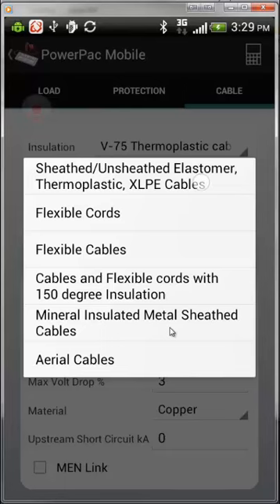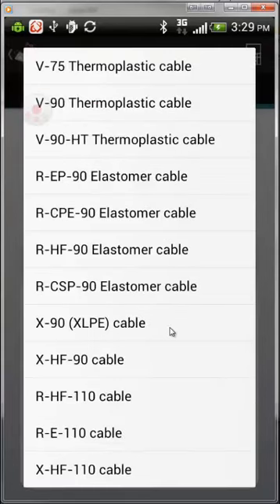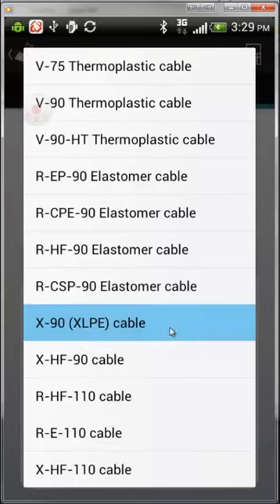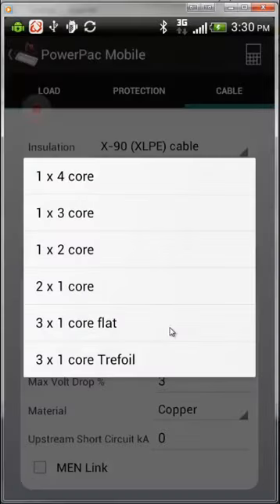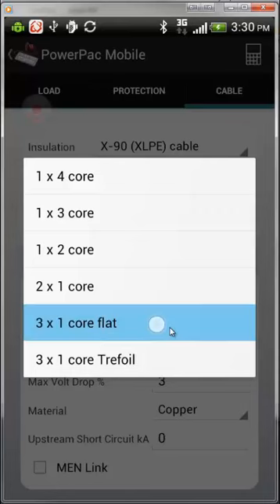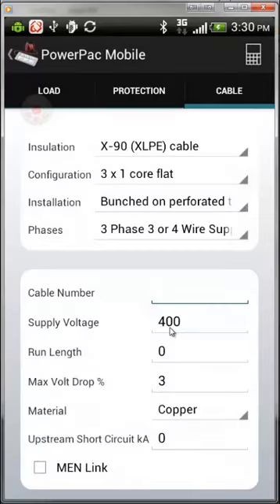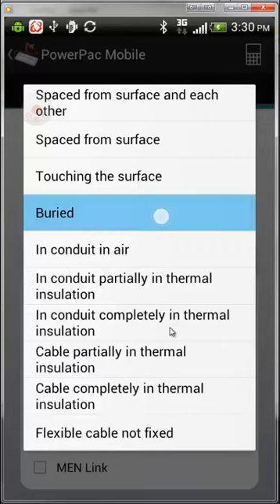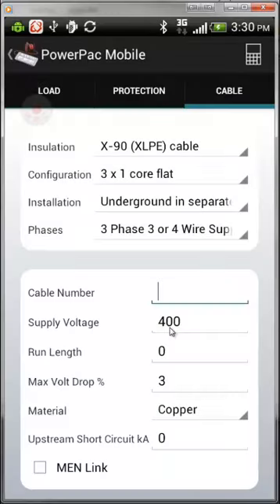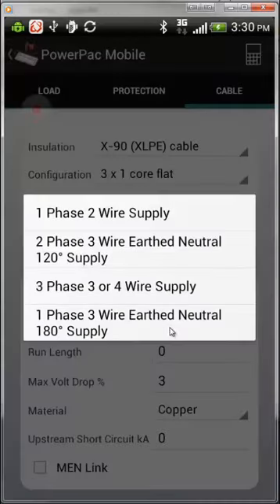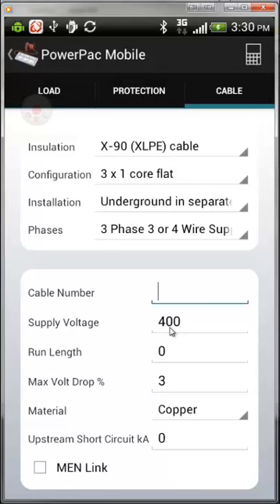Now go to Cable Information. Select your cable insulation — all cables from AS3008 are available here. Select the cable required and enter the configuration: we will install 3x1 core flat. Choose how it will be installed — we are going to bury it in separate conduits. You can also choose whether it's a three-phase or single-phase supply.